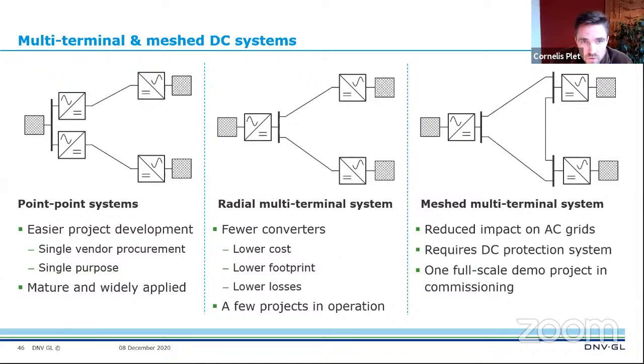An alternative to this could be the radial multi-terminal system, shown in the middle. This could serve the same transmission need, but we need fewer converters. We combine the two links on the left-hand side and have one converter to go out. This immediately leads to lower cost, a lower footprint, lower losses, and higher availability of the system as a whole. It also allows us, as in the example of a hybrid interconnector, to combine purposes and increase the utilization of the grid.